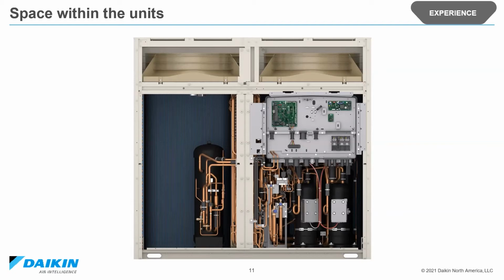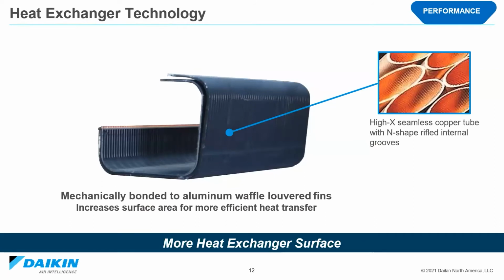Part of the new design includes refrigerant pressure and temperature readings via digital gauges. And this open design is also going to make it much easier to work on and maintain the units, also making it easier to clean your condenser coils. To increase the heat transfer capability of the condenser coils, the engineers added the N-shaped rifled internal grooves to the coil tubes. And this has allowed for a greater unit capacity and smaller overall footprint.